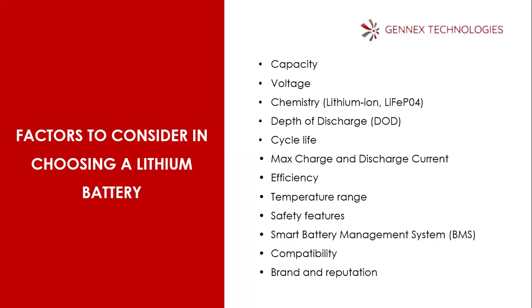So, the smart battery management system that you need to check, because the batteries naturally come with the BMS, which takes care of balancing the cells, making sure that the batteries are not overcharged, making sure that the battery is being monitored well when it's under discharge, when the temperature around it is high, when the internal temperature is high. So all these have been taken care of. So you look at the specification and check well with the manufacturer information. It's very important. If all these things are not there, then you may be buying a battery that may be dangerous to the environment.